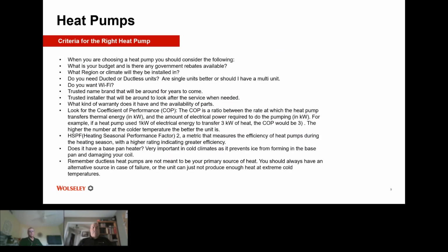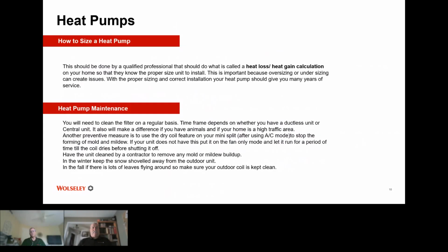It's the size of the heat pump. This should be done by a qualified professional who should do what is called a heat loss, heat gain calculation on your home, so that you know the proper size unit to install. This is important because oversizing or undersizing can create issues. In the heat pump case, bigger is not better. With the proper sizing and correct installation, your heat pump should give you many years of service.